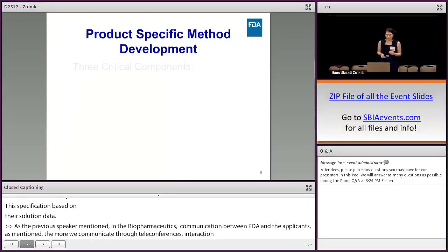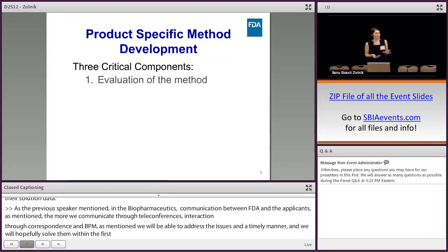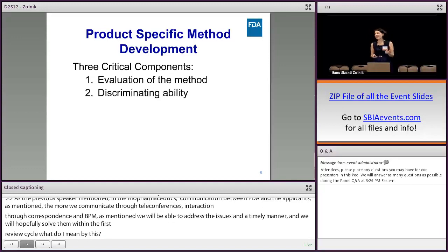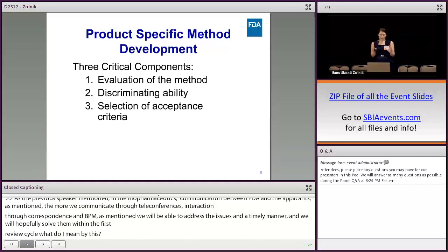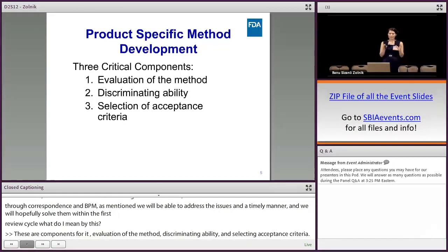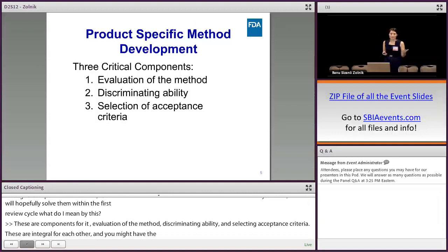Product-specific method development — what do I mean by that? There are three critical components for this: evaluation of the method, discriminating ability of the method, and setting the acceptance criteria. These three are integral to each other. For example, you may have the right method with discriminating ability; however, if we don't set the specification at the right time point, we may lose this ability of the method.